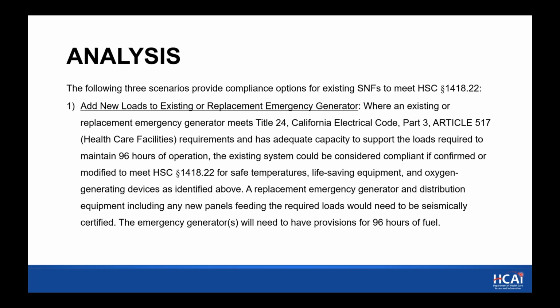So number one, adding new or existing loads or replacing the emergency generator. Where an existing or replacement emergency generator meets Title 24, California Electrical Code Part 3, 517 healthcare facilities requirements, and has adequate capacity to support the loads required to maintain 96 hours of operation, the existing system could be considered compliant if confirmed or modified to meet the safe temperature, life-saving equipment, and oxygen generator requirements. A replacement emergency generator and distribution equipment, including any new panels feeding the required loads, would need to be seismically certified. And the emergency generators would need to have provision for 96 hours of fuel.